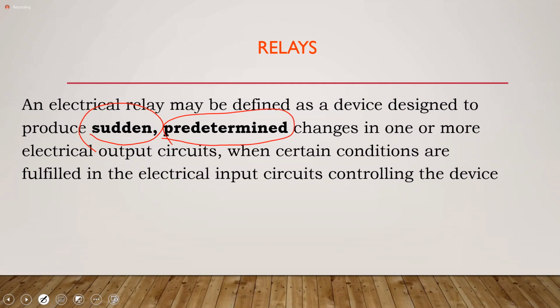In doing so, you may end up causing the current on a particular feeder to go beyond what its normal maximum is or should be. You with me? Now, you don't want the system to shut down because you are carrying out that switching operation. So whilst the overcurrent relay will detect that, yes, the current has exceeded the value that it ought to, or exceeded this predetermined value, it will react slower to that overload.